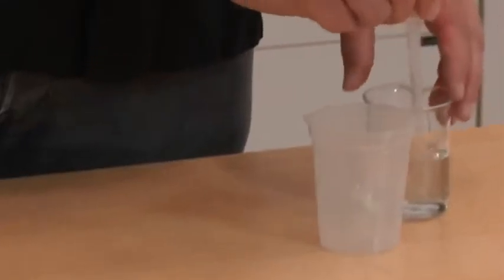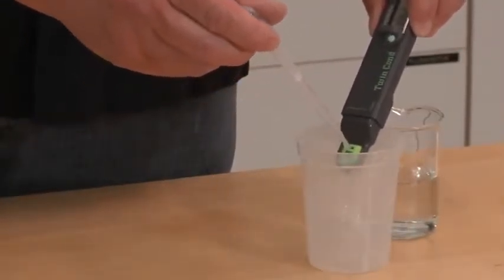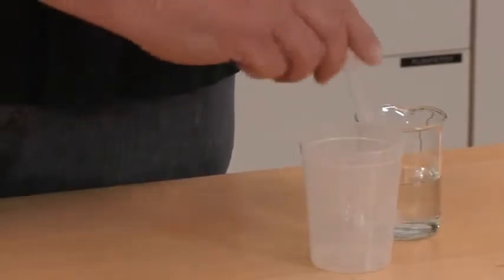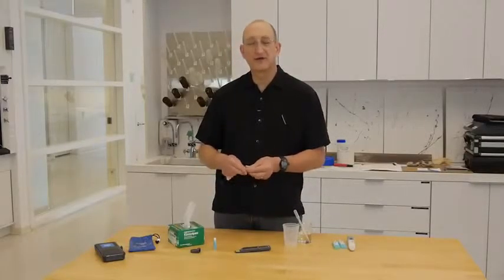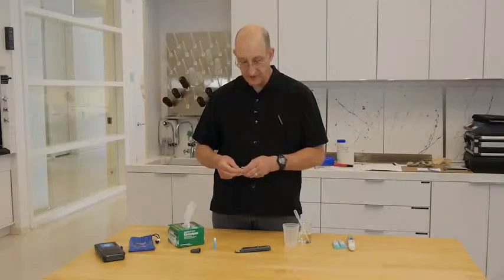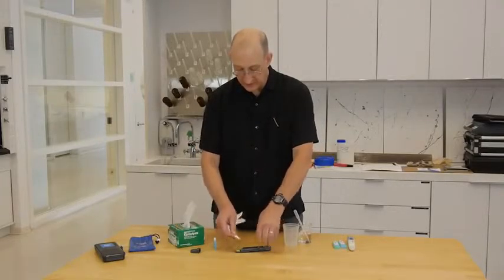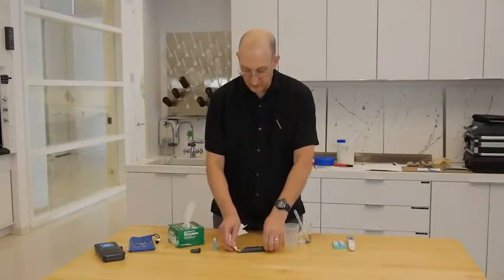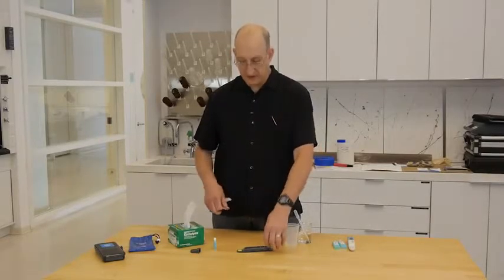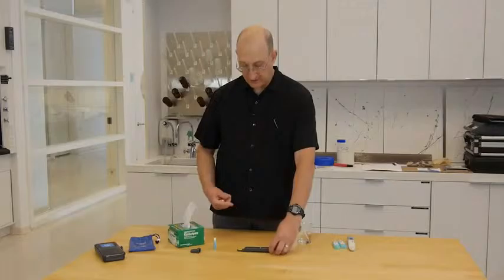We then rinse the electrode head with deionized or distilled water and just flush it out. Because dilution matters for conductivity meters, we want to make sure we always dry the sample well with a little piece of Kimwipe to get the water out, so we don't dilute our next reading.